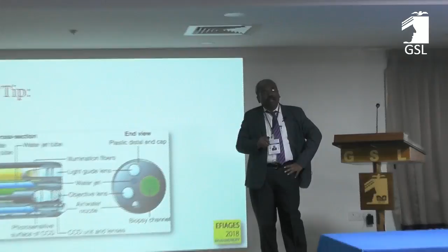As well, the newer generation scopes which are upcoming have a direct LED tip light source. Whatever scopes we currently have all have a light source in the processor, from which some form of transmission through optical fiber bundles has to happen. So optical fiber bundles, depending upon the type of procedure and the type of scope, you may have 2 light bundles or 1 light bundle. As well, you may have other special channels depending on what scope you are using.